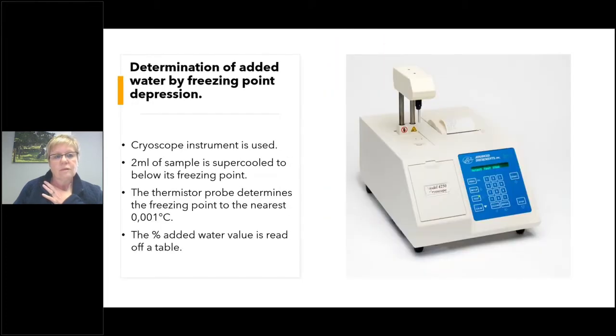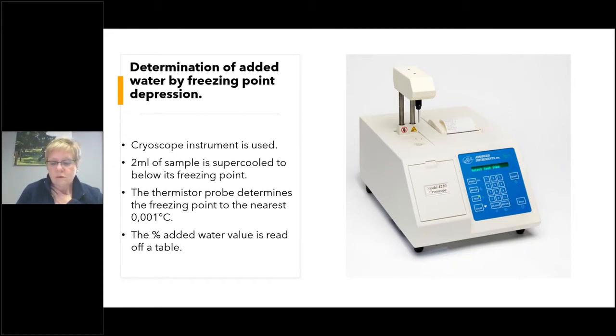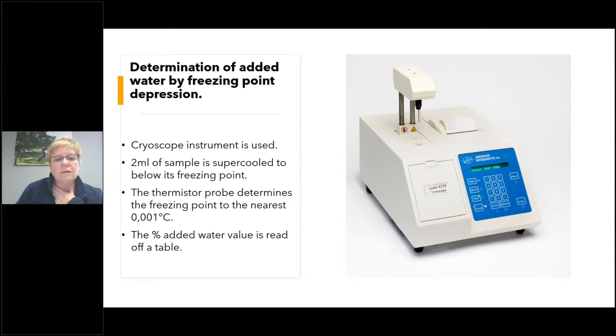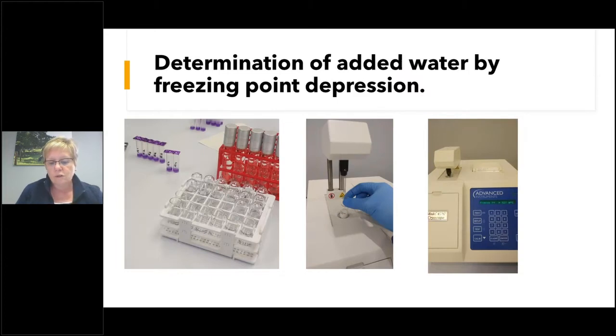The next test is the freezing point test, done with a cryoscope. This test is done to check for added water in a sample. Two milliliters of sample is supercooled below its freezing point. The thermistor probe determines the freezing point to the nearest 0.001°C. The added water value is then read off a table. This can also be done by calculation using the IDF method — there is a calculation to determine the added water percentage.